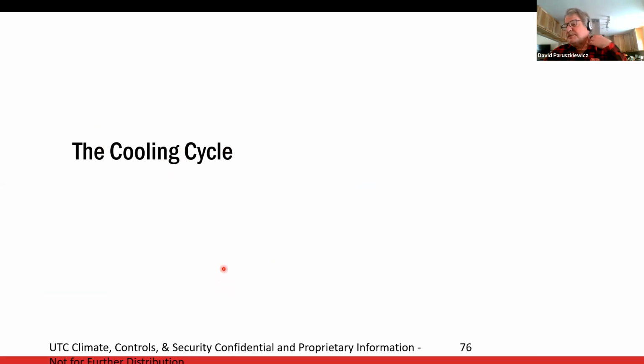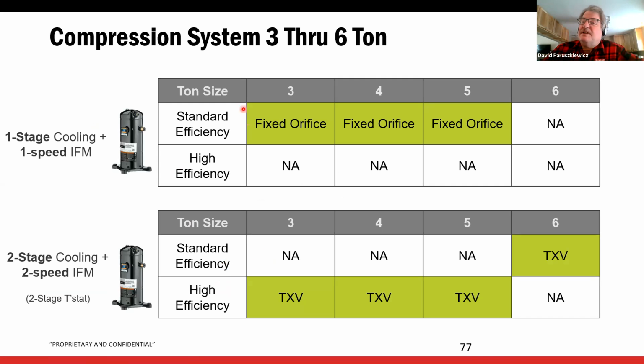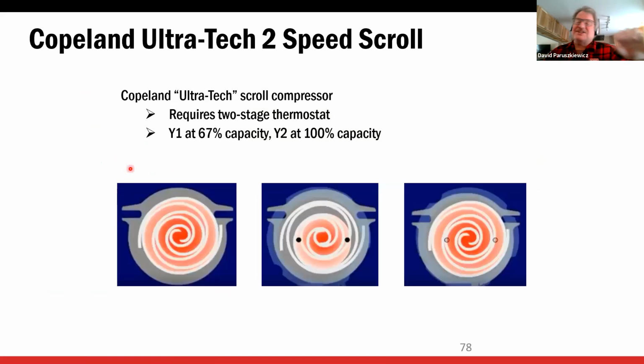the cooling cycle we're going to jump into now. So a few things I want to talk about now. The small Axion units are all single stage cooling except for the 6-ton, which does use the 2-speed scroll. And some of the smaller big units use the 2-speed scroll. Now we're going to talk about this for a second. It's actually not 2-speed. The scroll plates have a couple of bleed holes in them. So what happens is when we're unloaded, we used to call them unloaders on big semi-hermetics, but what happens is we bypass some of the suction and hot gas, so we're not pumping as much.